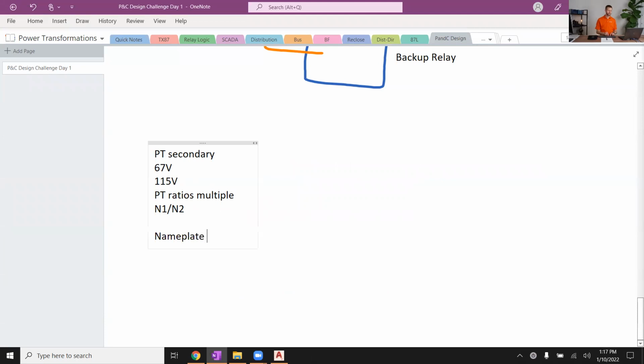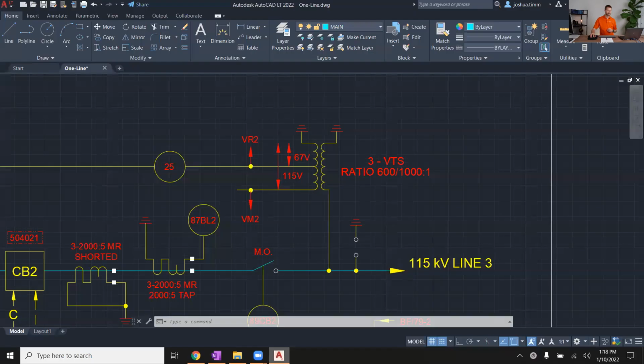Yes, so you have a nameplate ratio, but the reality is that the nameplate primary voltage may or may not exactly match your system's nominal operating voltage. And keep in mind that your system's voltage is always going up and down, plus or minus 5% as well. So you do need to take the nameplate ratio. It may not be exactly 67 volts. Say this was the same PT, but it was a 100 kV line instead of a 115 kV. I don't know if that's realistic, but let's just use it for hypothetical sake, right?